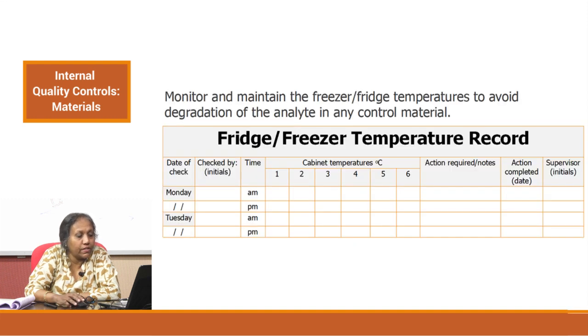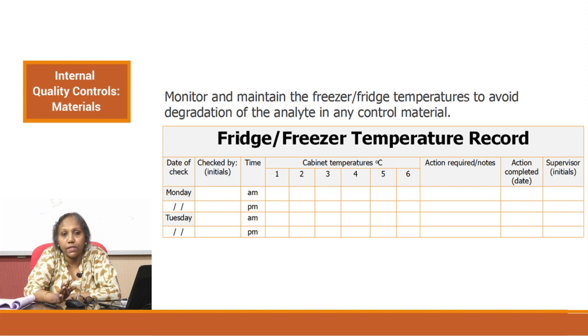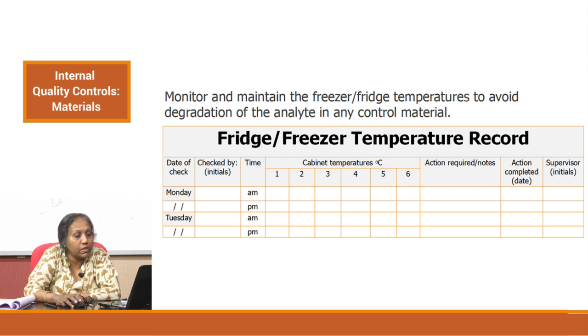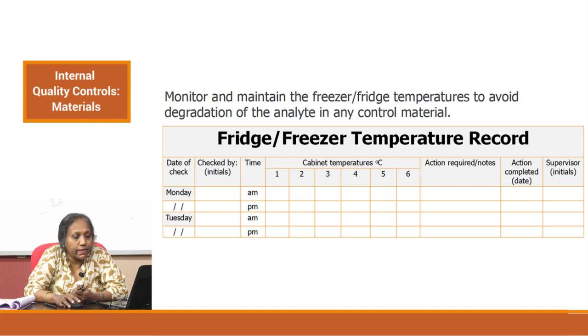The fridge and freezer temperature is very important. Before reconstitution, most lyophilized QCs are kept at 2 to 8 degrees centigrade. After reconstitution, they are stored in the freezer. It is extremely important to monitor the fridge and freezer temperature and to have thermometers that monitor fridge and freezer temperature that are calibrated, so you are sure about the performance of this equipment. Take care to store the control material carefully as per the manufacturer's instructions. Remember — only stable QCs are useful to detect instabilities in the analytical system.